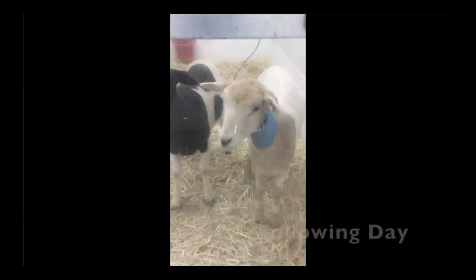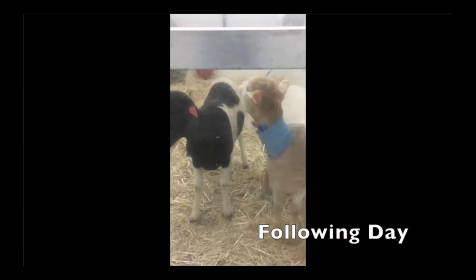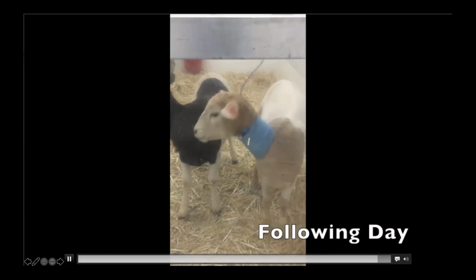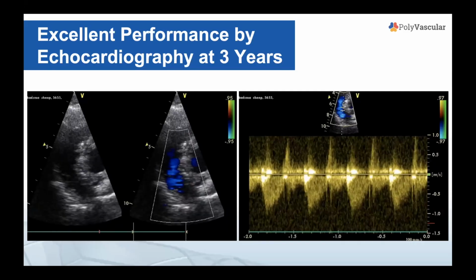And immediately the valve is functioning well, and we have no leak, and the sheep are up and about within a few hours. Now, as I said, we've completed a 3-year chronic animal study showing that the valves are performing beautifully with almost no narrowing, almost no leaking, and we have just explanted our valves.